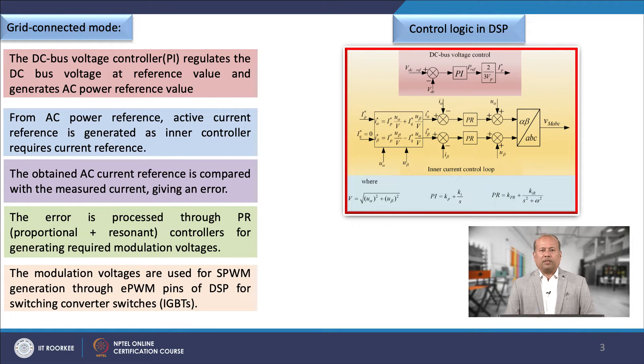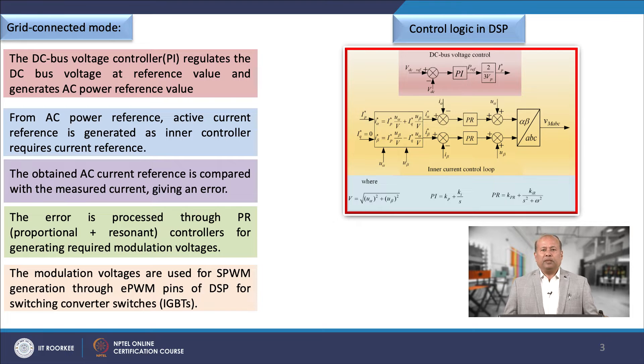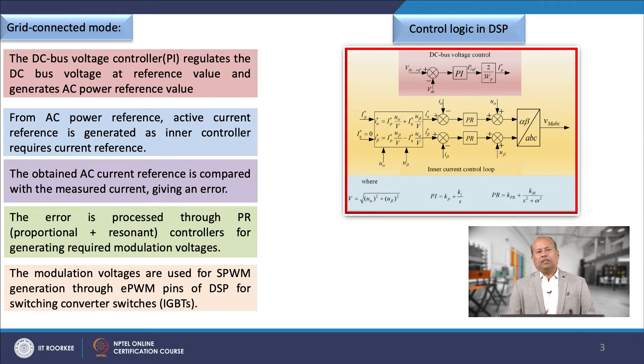The error is processed through proportional plus resonant controllers for generating the required modulation voltages. The modulation voltages are used for SPWM generation through EPWM pins of the DSP for switching converter switches, commonly IGBTs. The control variables of the PI controller as well as the PR controller can be obtained through proper tuning, ensuring that the stability margin should be sufficient.